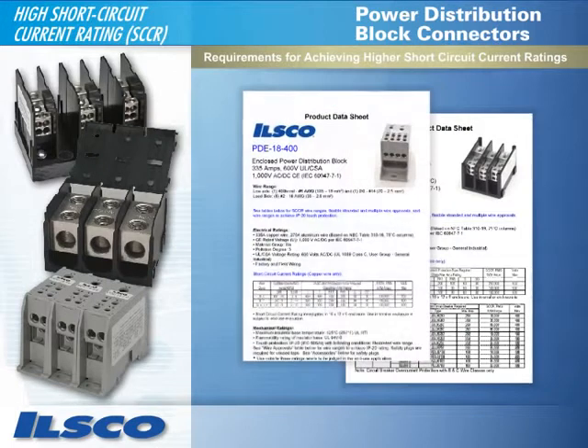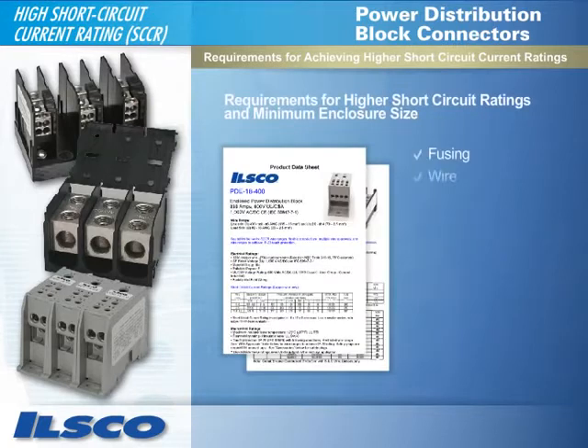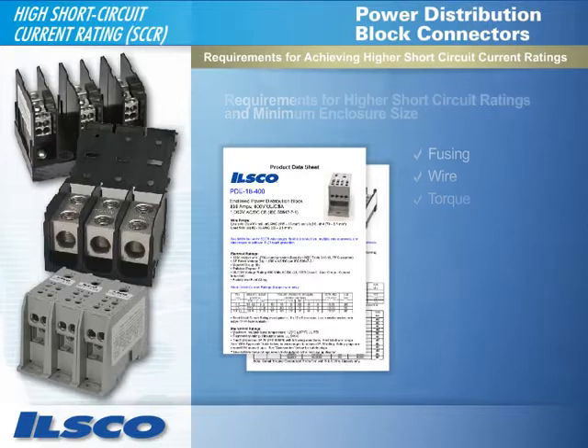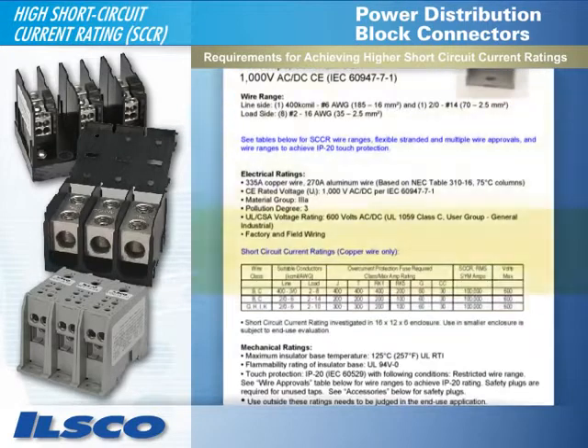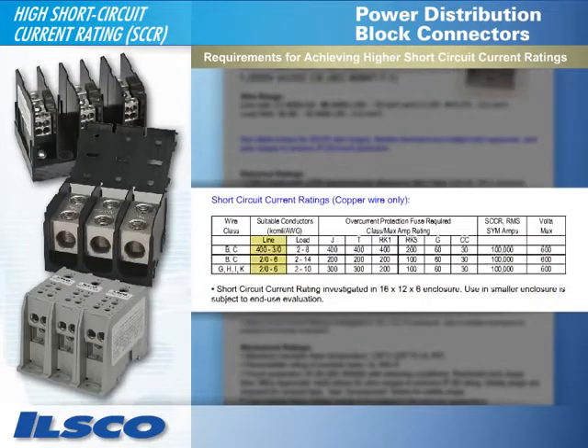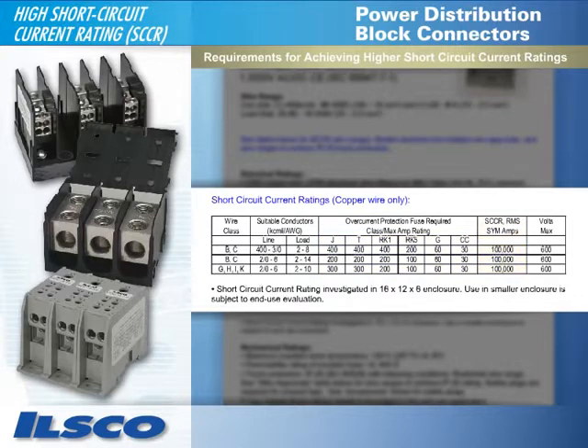The product data sheets for ILSCO's high SCCR blocks provide charts for determining the correct fusing, wire, and torque requirements for higher short-circuit current rating and minimum enclosure size. The short-circuit current ratings chart allows you to determine the line and load conductors, along with overcurrent protection fuse combinations needed in conjunction with the new power distribution blocks to achieve a high SCCR. Each line in this chart must be read independently to determine a working combination of components.